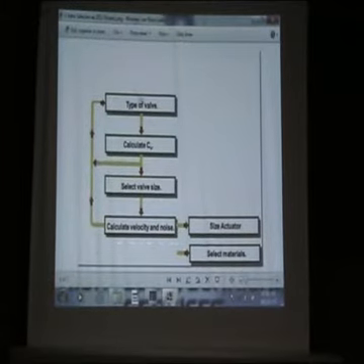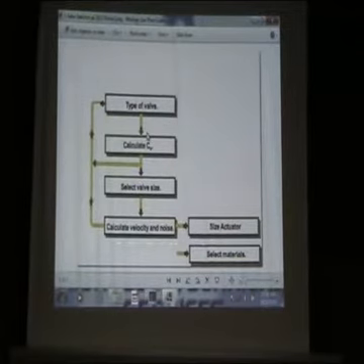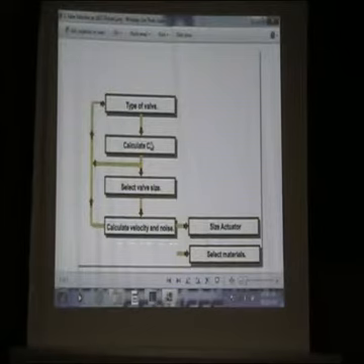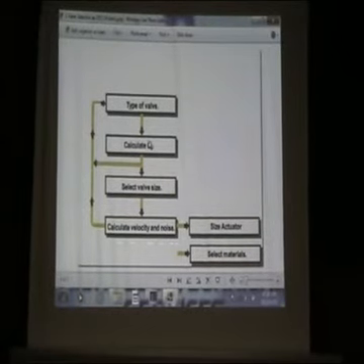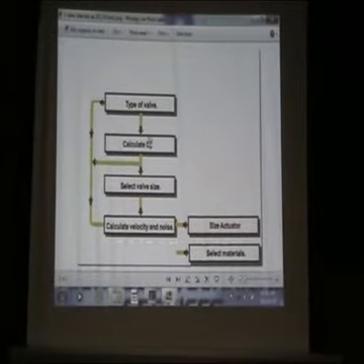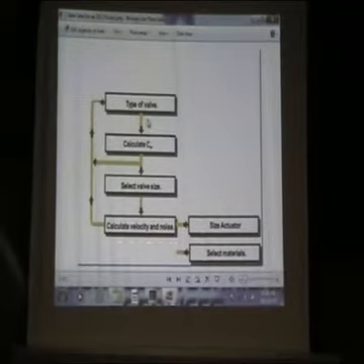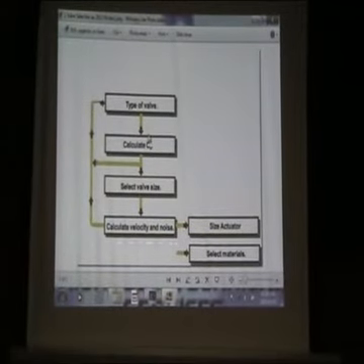Alright, type of valve. If you want to select the type of valve, first of all you need to know the Cv, just getting to the size. Let me put it simply: Cv is the amount of water passing through a valve in gallons per minute, with a given pressure drop. That's technical, you'll get that when you get to globe valves later. Cv is just the capacity of the valve, how much flow the valve can handle.